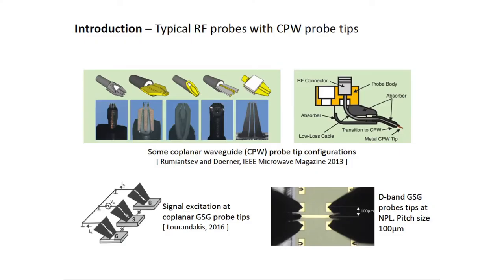This slide shows typical RF probes with CPW probe tip configurations — this is actually from a paper published by a previous speaker. Although they always have the GSG probe tip configuration, they may have different styles from different manufacturers. It shows what's inside these probes: you have a coaxial input and then a CPW output. This photograph shows the D-band (110 to 170 GHz) GSG probe tips at NPL. The pitch size is 100 micron — that's the center-to-center distance between signal and ground.